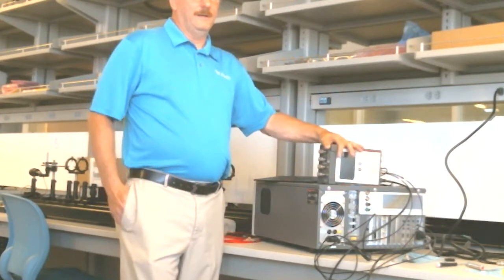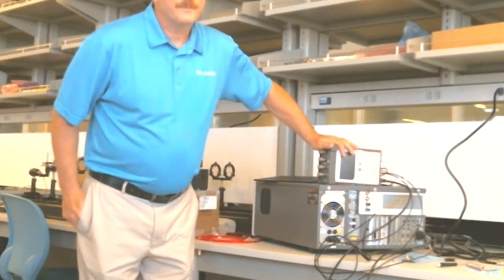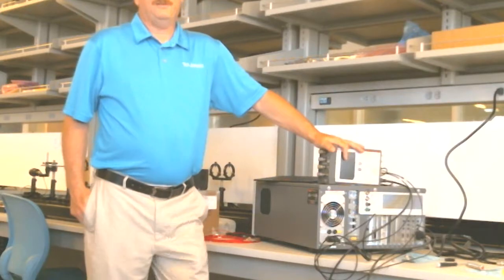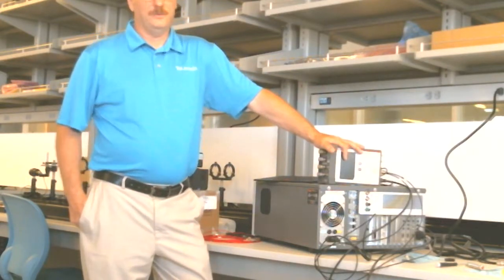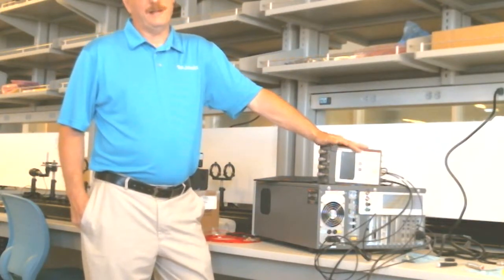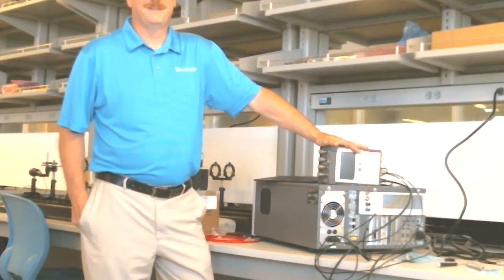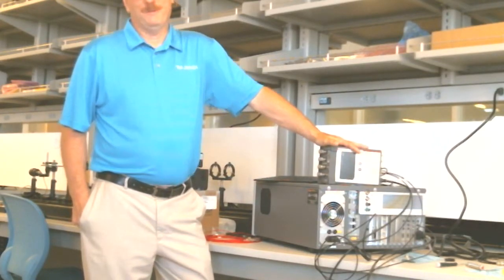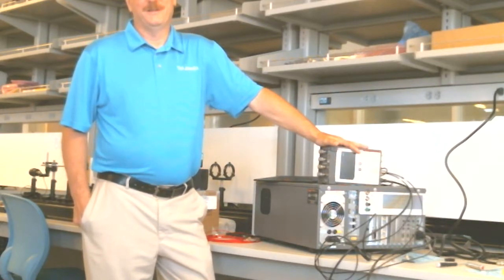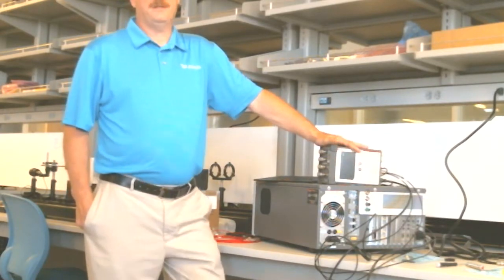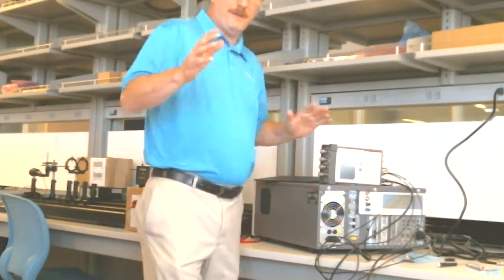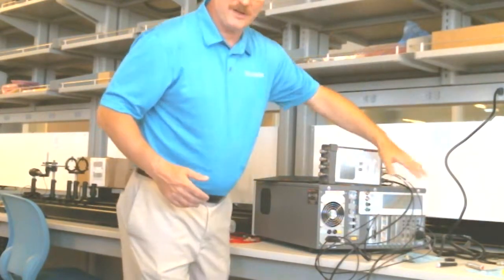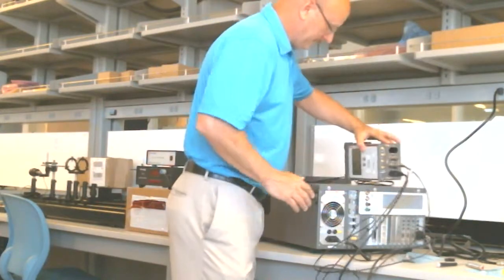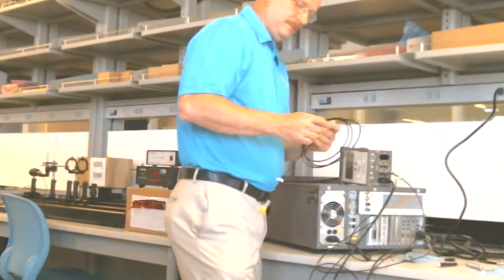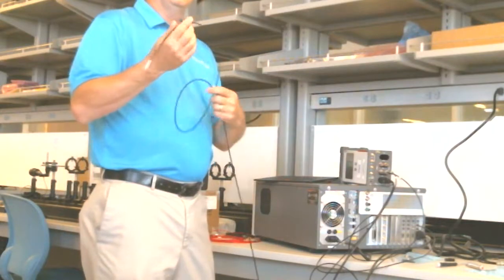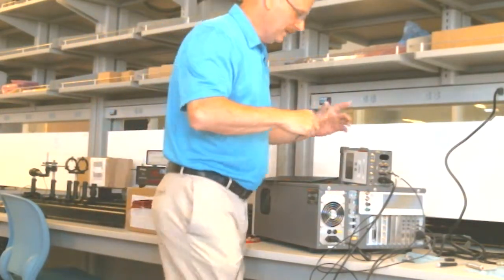And what is the reason that we have preamps for SMU1 and pass through for the others? Higher sensitivity current measurements. Yeah, if you need to measure attoamps, you'll need to use channel 1. You can measure femtoamps without the preamps. So they are matched together, calibrated as a pair. Not only as a pair, but in the slot that they're in. So you can't move these cards around. Don't even think about it. So I think the preamp is more expensive than the pass through. Yes, it's very much so.